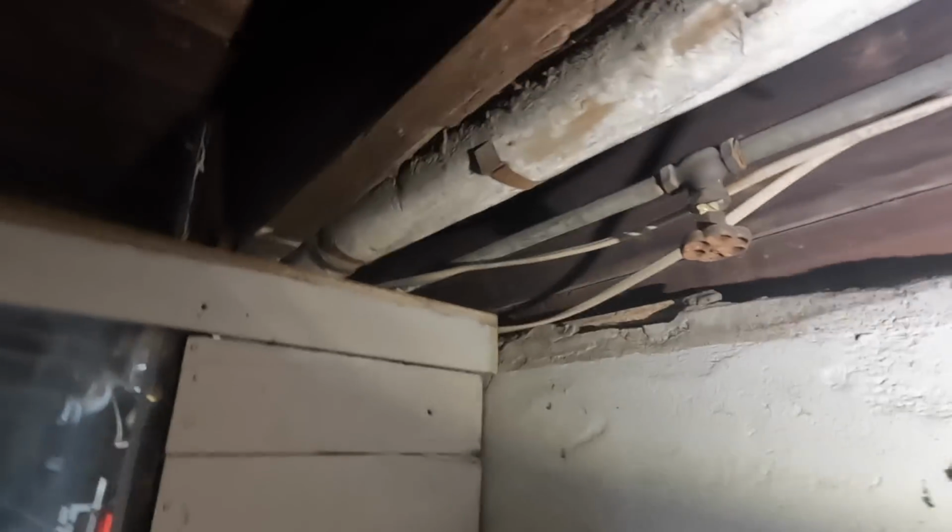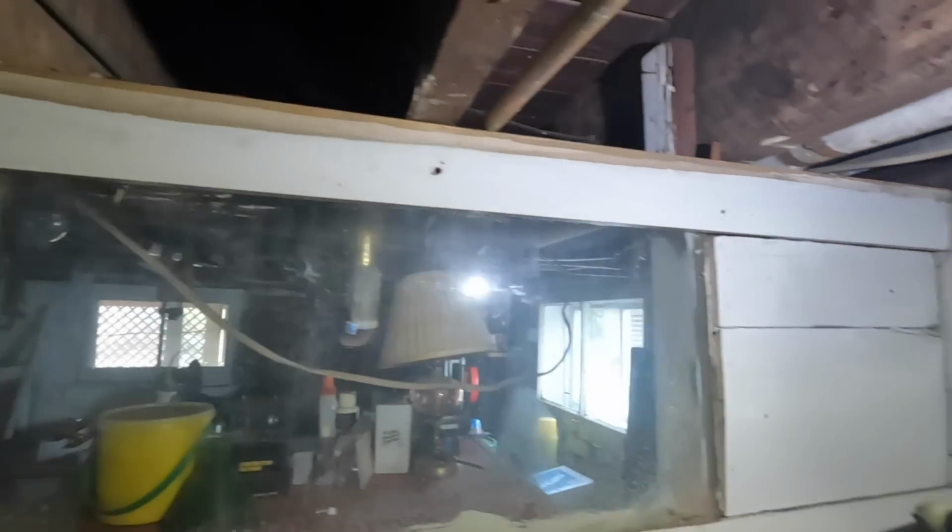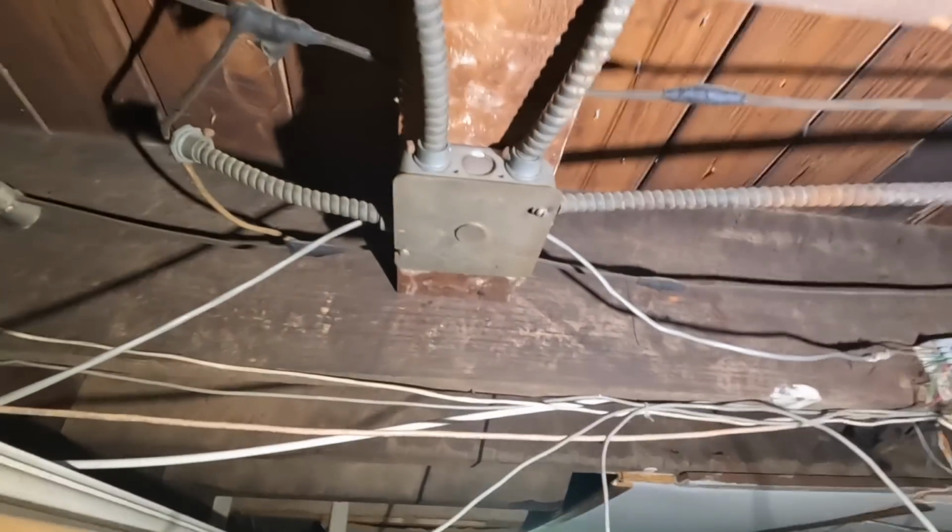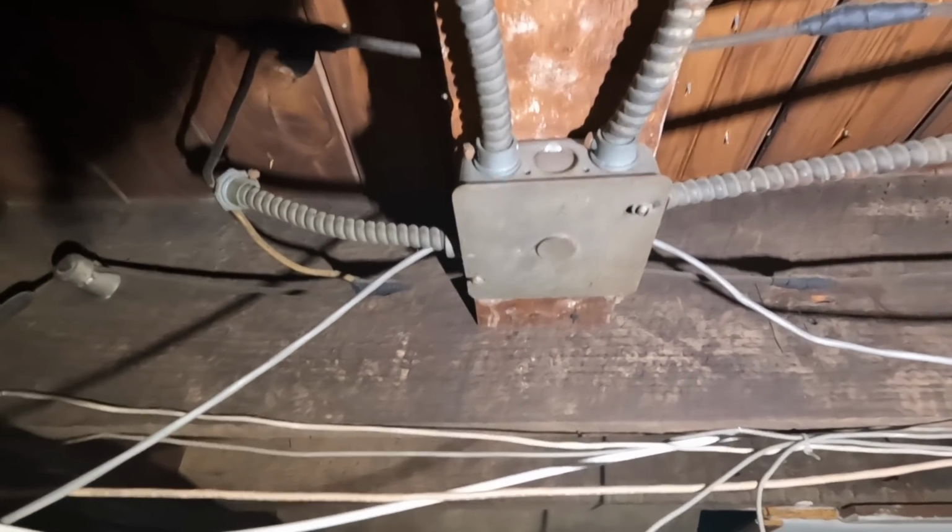I've replaced two or three of these boxes here. One of them was a two-gang metal gem that we put in, and then two receptacles in the living room. We wound up making the hole cut out in the baseboard a little bit larger, and we put in plastic boxes. So there you can see how they extended it. That 1900 box was added later on. It was just connected to the knob and tube circuit, and then they ran armored cable out of that box to new things down in the basement, or to the first floor, wherever the stuff was going.